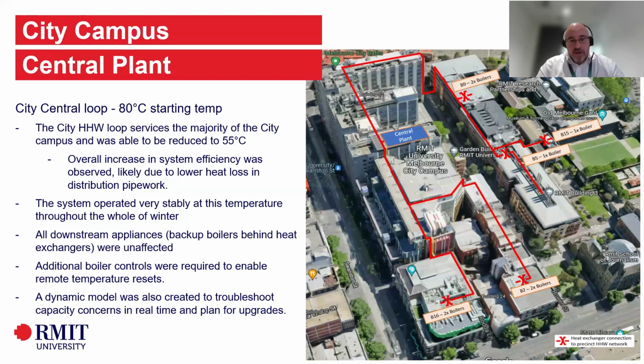All downstream appliances were unaffected. We did not see a material increase in complaints, but we did need additional boiler controls to enable resets and contingency planning in the event there was concerns. We did also develop a dynamic model so that we could troubleshoot any capacities, and the dynamic model looked at all the various pipe network flows, so we could see if there was a complaint in an area, if we were able to adjust in a fairly dynamic manner.